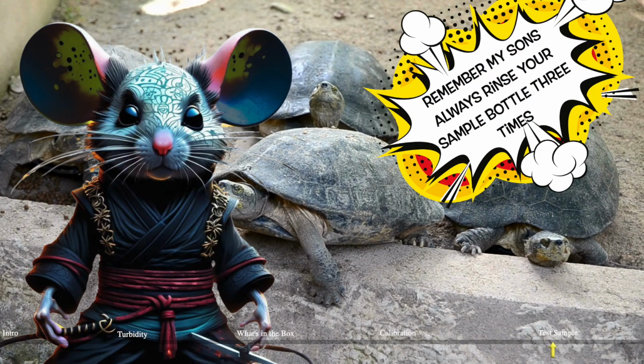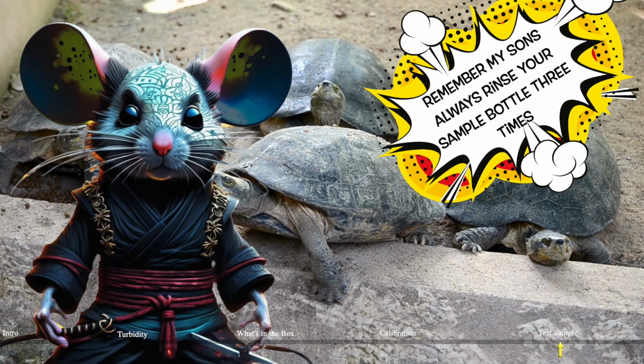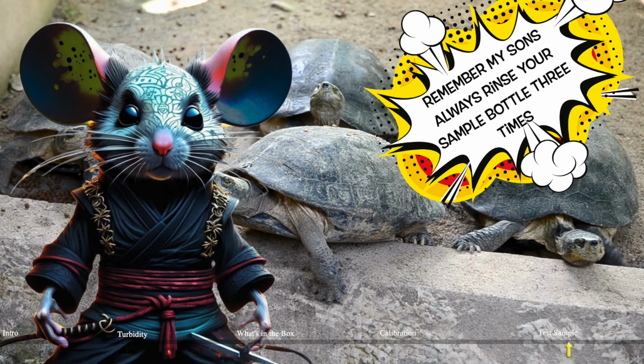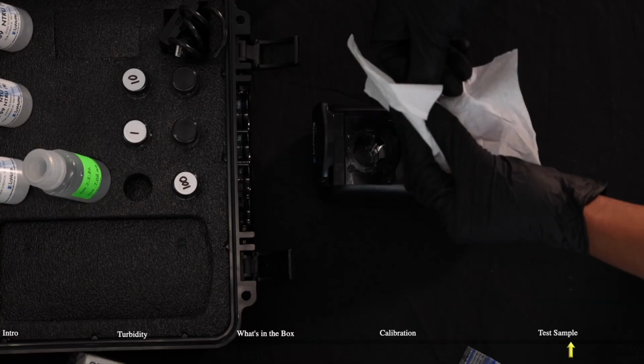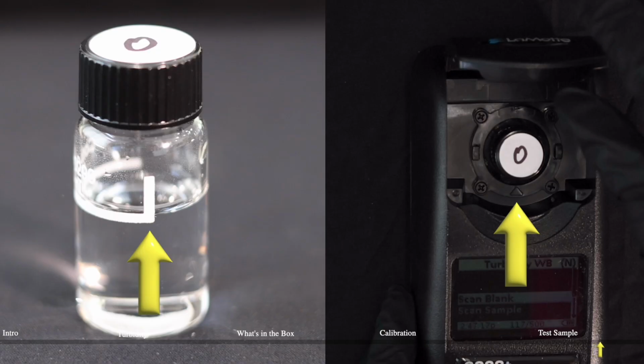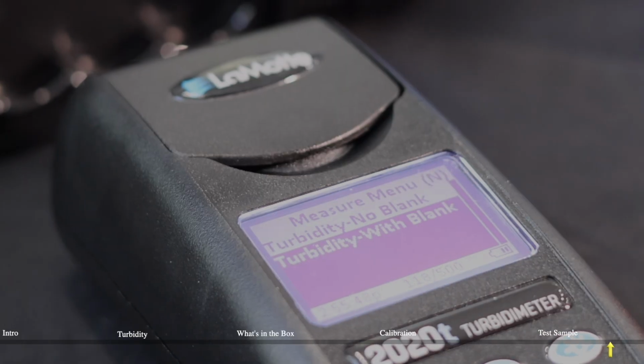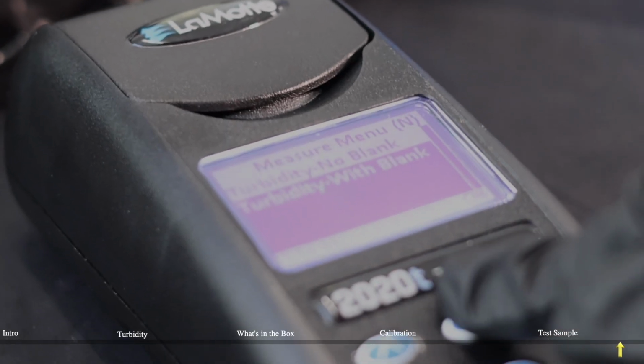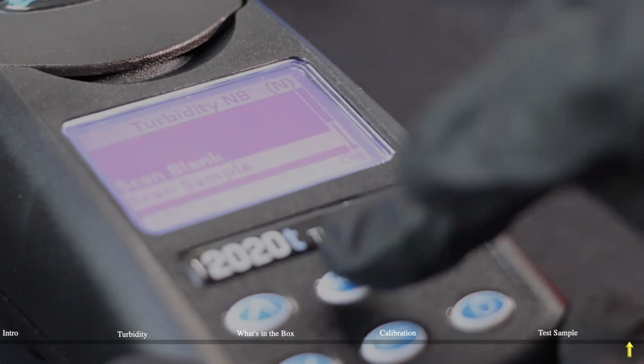You still want to remember, it is always best to rinse your sample tube with your collection just as you did with the standards. Once you have done that, go ahead and give it a wipe with the cloth and insert your sample tube back into the meter. Again, lining up the arrows with the white line. This time, you will go straight to Scan Sample without blank, and then press Scan Sample.